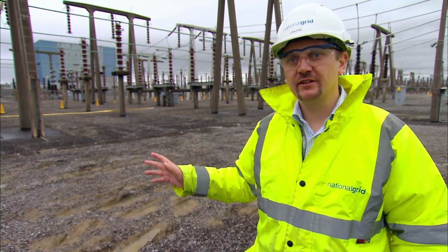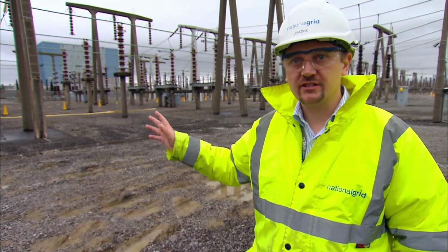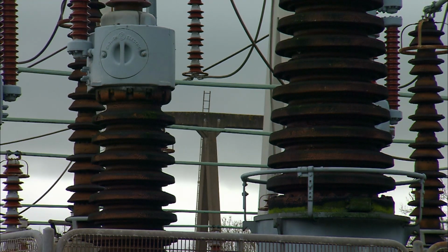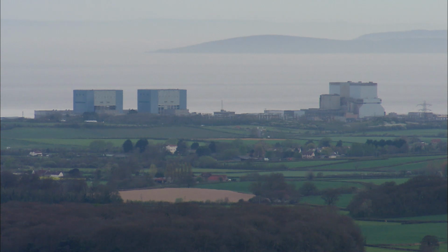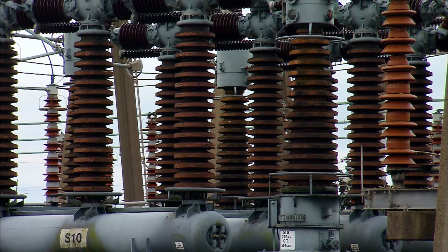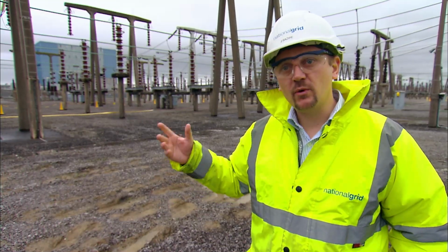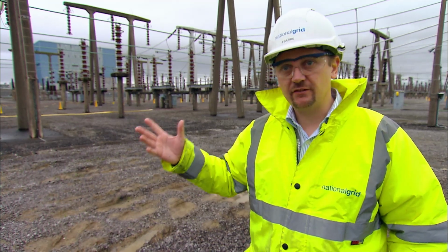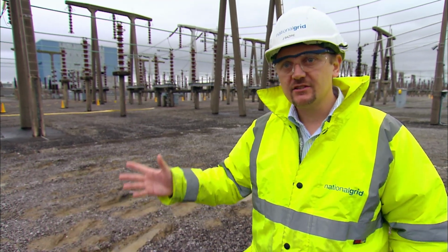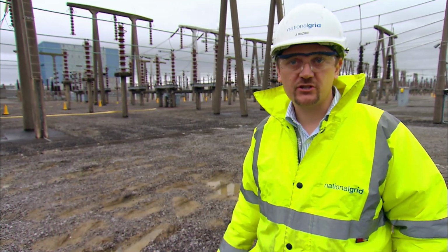It's imperative that we keep the insulators clean. Those insulators are the brown porcelains that you see suspending the busbars. We're right near the coast, off the Bristol Channel here. We get a lot of salt pollution, and that salt pollution builds up, and the one thing that we do not want, we can ill afford, is a flashover. So this is why we're carrying out this water washing.